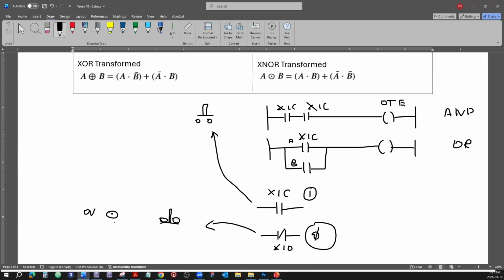Applying 0 volts, or not applying 24 volts, because the PLCs work on 24 volts. We drilled that a couple times during the lectures in class. If we have 0 volts applied to the physical input, that instruction is going to pass the logic through and is going to give the bit of 1 on the output energized. And if the output energized sees the bit 1, it is going to apply 24 volts to the physical output.